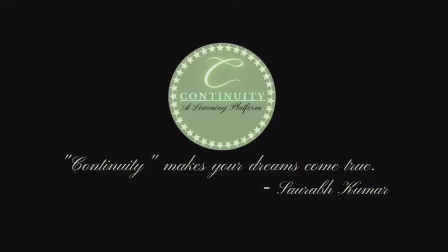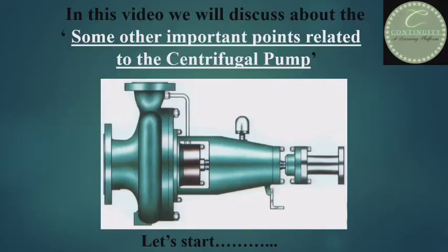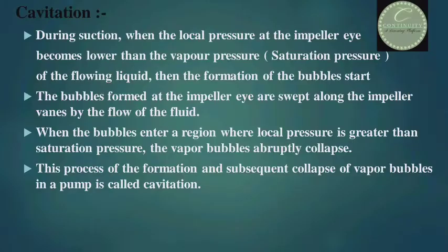Welcome to the Continuity channel. Today I will discuss some important points related to centrifugal pumps, like cavitation, net positive suction head, pump characteristic curve, lubrication, disassembly and assembly of pump, and its starting procedure. Let's start. First, I shall tell you about cavitation. During suction, when the local pressure at the impeller eye becomes lower than the vapor pressure — the saturation pressure of the flowing liquid — then the formation of bubbles starts.